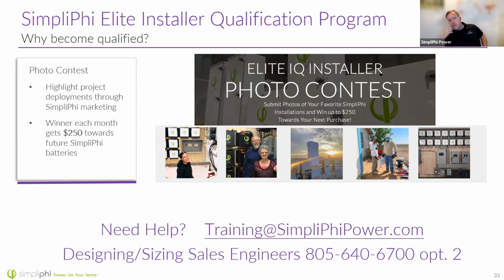What about this, Chuck? I always thought about this: what if I ship you some batteries at, say, 51 volts, and the batteries in your system are currently floating at 54 volts? Could we discharge the existing batteries down to an acceptable level—remember, within 1 volt—so discharge the old batteries down to 52, turn off any charge cycles, and then incorporate the old batteries? So rather than charging up the new batteries, you're discharging the old batteries and then marrying them. I'm not sure, it seems like it would work. That would work, yeah.